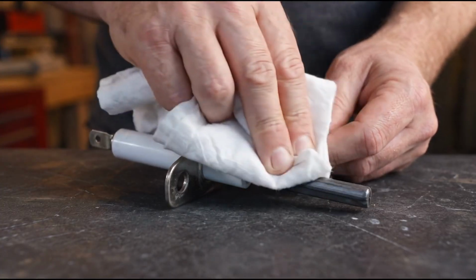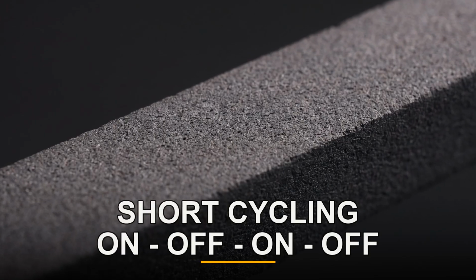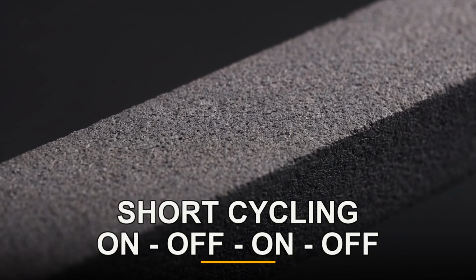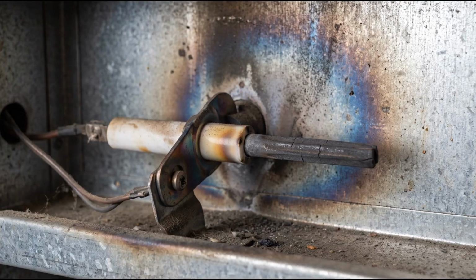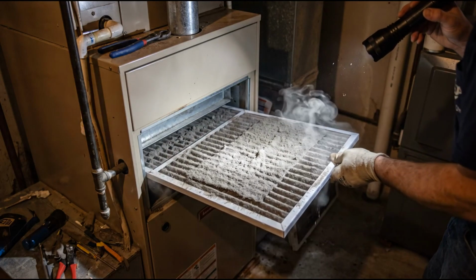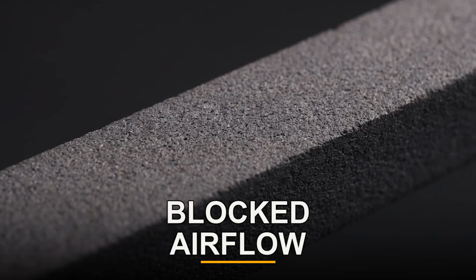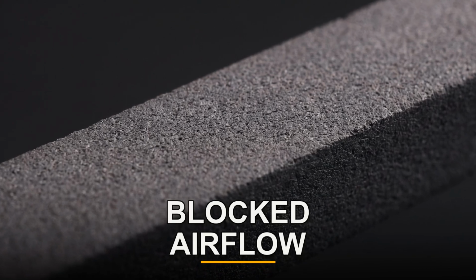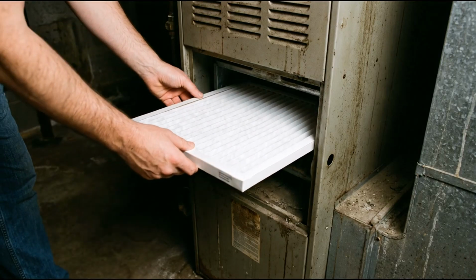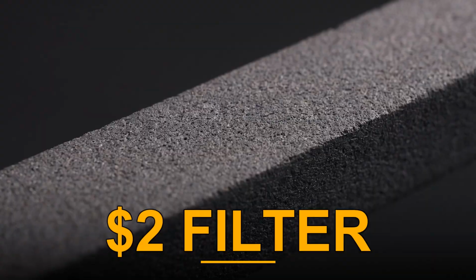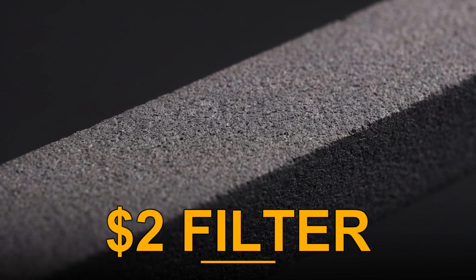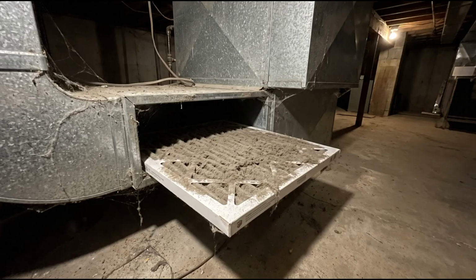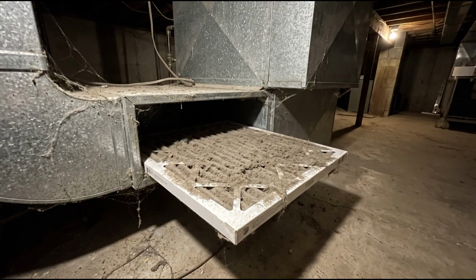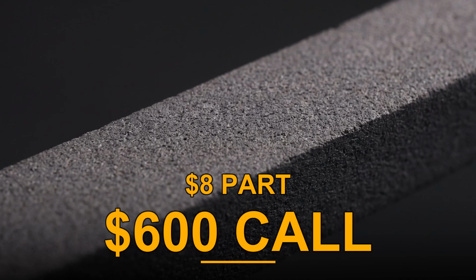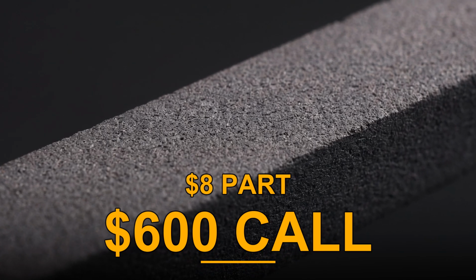And one more habit while we are here: a furnace that short cycles, kicking on and off constantly, is putting triple wear on the igniter. Short cycling usually traces back to a dirty filter choking the airflow and tripping the overheat limit. So the cheapest igniter insurance there is the $2 filter, changed every season. Starving the furnace of air is how $8 parts and $600 calls get manufactured.